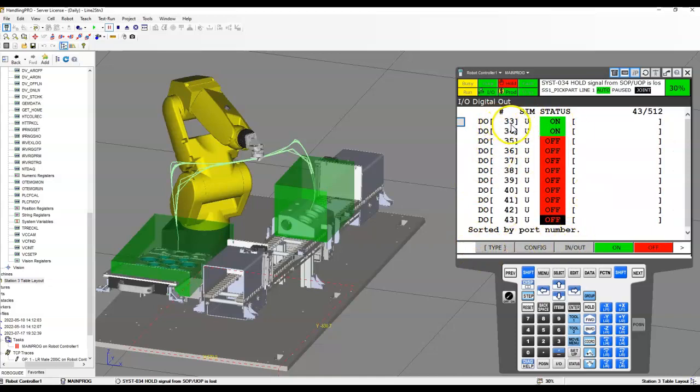So let's move on to observe the DOUT, which are the signals given by the robot to the PLC whenever there are changes in these two world zones. For Fanuc, whenever the robot enters the world zone, this tag is turned off, and it is on whenever the robot is outside the world zone. So let's observe.